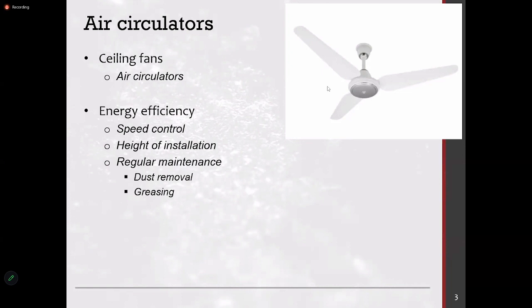The key thing is on these blades, you have to ensure regular cleaning because there is dust deposited. You will see a lot of fans with dust, and in my place we are also having a lot of problems with corrosion by the sea, because if the blades are metal blades, then they tend to corrode. If the blades are not sharp enough, if the thickness has increased, then the resistance to air is high, so the speed reduces. And when dust is collected, the weight of the blade increases. So even though it's dust, once it's deposited, the weight increases. So a slight change in the shape or the thickness or the amount of dust on the fan will actually increase the power consumption and reduce the output.